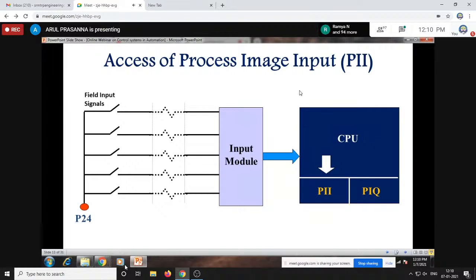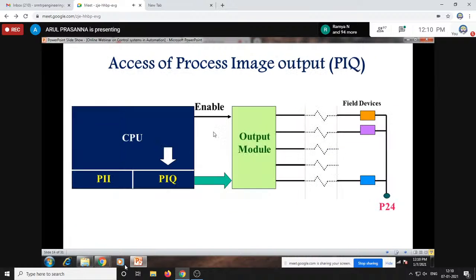Now let's see one by one: this is the PII chart, and this is the PIQ chart. The CPU goes through the program and checks whether your input is used to turn on any output, then updates the PIQ chart. That is reflected as a 5 volt output, which is again converted into 24 volts and made available to the PLC field devices. This is the process image output chart, and the CPU communicates with both PII and PIQ.